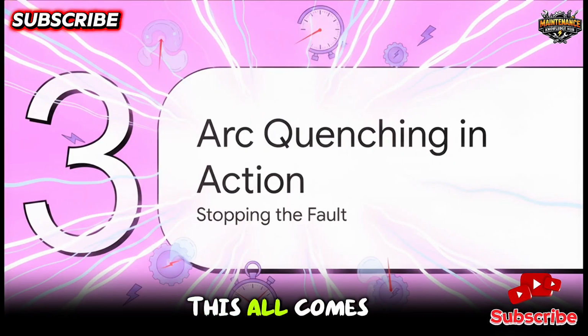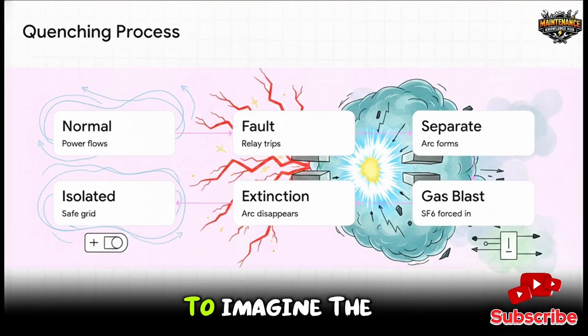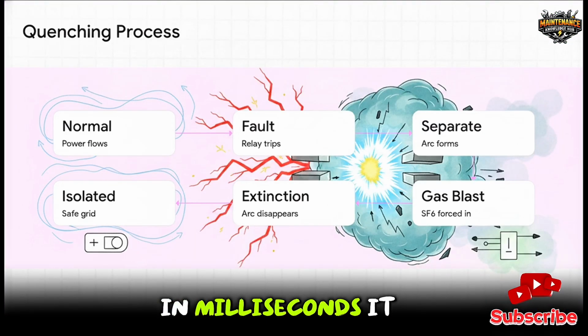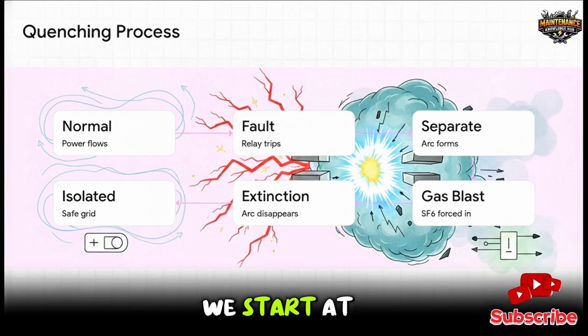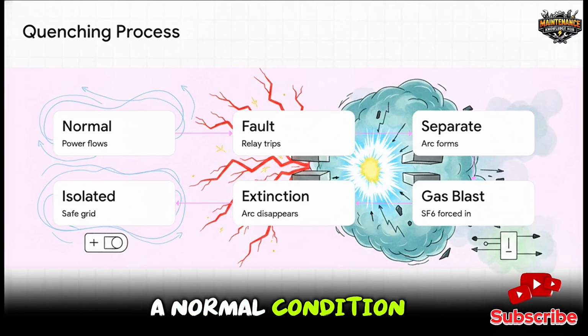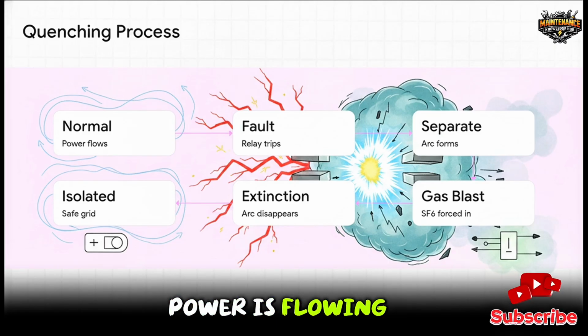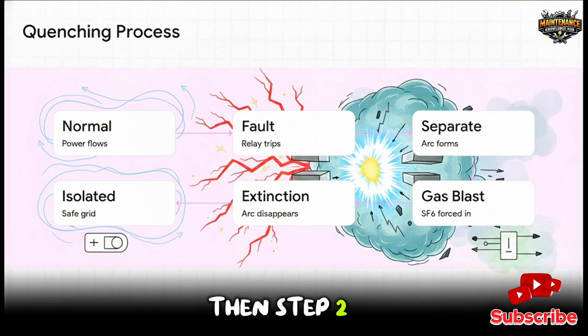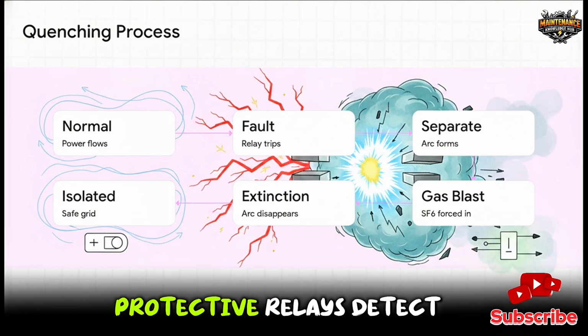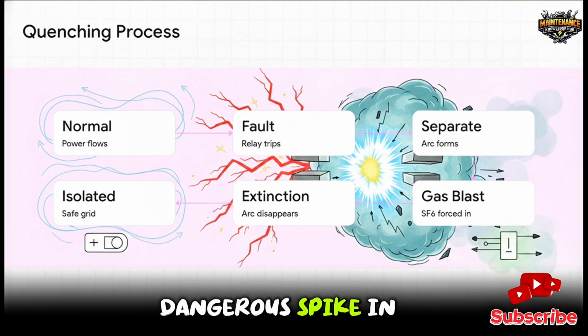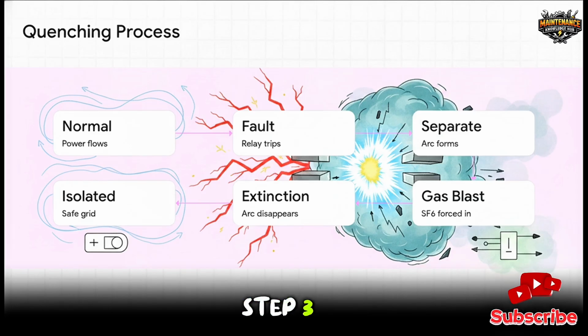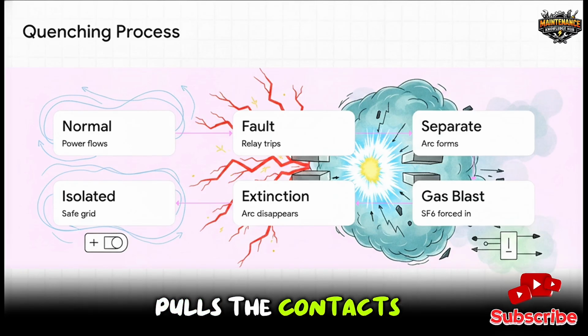All right, let's see how this all comes together in Section 3, Arc Quenching in Action. I want you to imagine the clock ticking here in milliseconds. It is incredibly fast. Here's the rapid 6-step sequence of arc quenching. We start at Step 1 with a normal condition. Contacts are closed, power is flowing happily. Then, Step 2, a fault occurs. Protective relays detect a massive, dangerous spike in current and instantly send a trip signal. Boom, Step 3. The mechanism aggressively pulls the contacts apart.